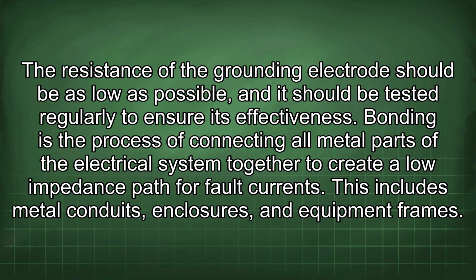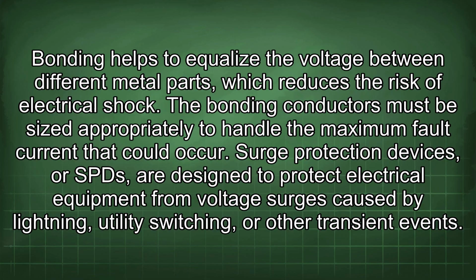Bonding is the process of connecting all metal parts of the electrical system together to create a low impedance path for fault currents. This includes metal conduits, enclosures, and equipment frames. Bonding helps to equalize the voltage between different metal parts, which reduces the risk of electrical shock. The bonding conductors must be sized appropriately to handle the maximum fault current that could occur.